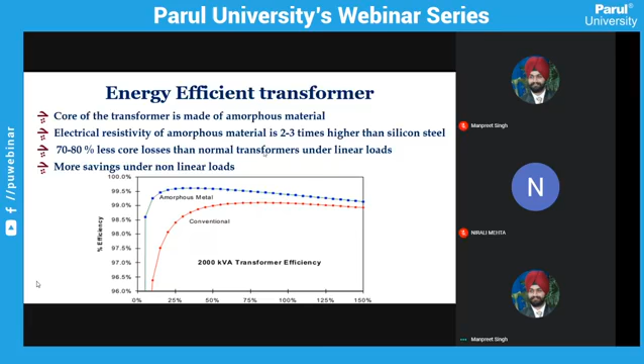Earlier, there was no rule for how much loss a transformer should have, but scientists and engineers continuously worked to reduce losses. In 2014, government made a standard, like star labelling, called IS 1180-1 2014 for distribution transformers, mentioning 3 types: efficiency level 1, level 2, and level 3, specifying for a particular kVA rating what percentage loss the transformer should have.